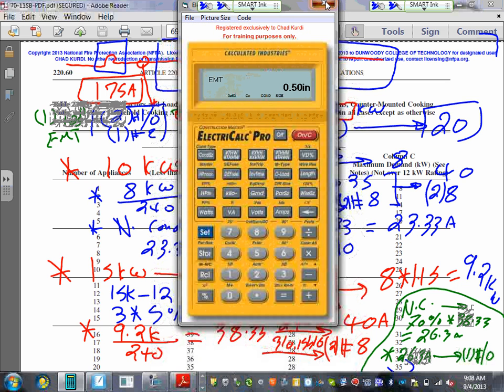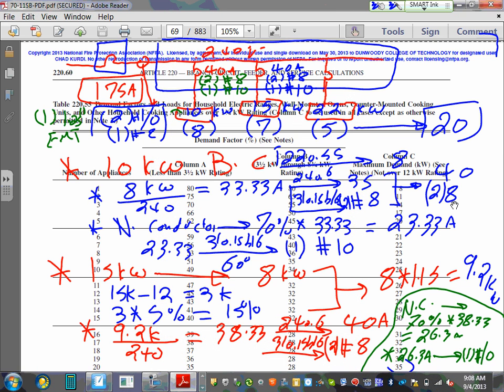Okay, so did you guys see that? So now I'm going to pipe it. So my pipe for this one is going to be half inch EMT, and this one is also going to be half inch EMT. So I piped it with half an inch EMT. They're the same size. Any comments, any questions for the branch circuits? The last thing I want to do is the last branch circuit.